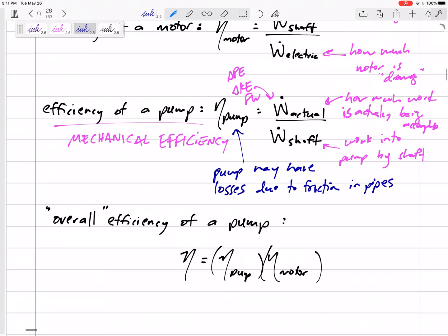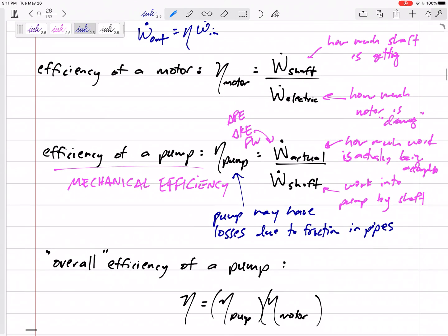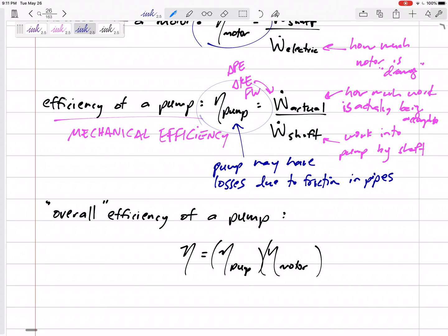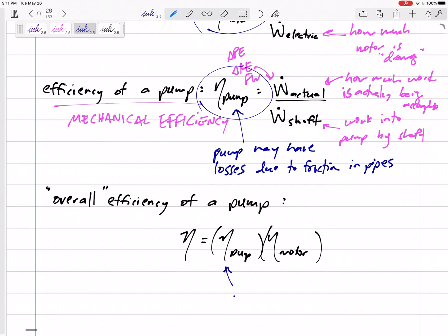The overall efficiency of a pump, if you have a motor that is driving a pump, would be the multiplication of both of those. For example, if you've got a pump that's 90% efficient, we've got 0.9, and a motor that's 90% efficient, then the overall total efficiency would be 81%. If both of those are 90%, we lose a little bit here, we lose a little bit there. Multiply the efficiencies together to get the overall efficiency of a pump.